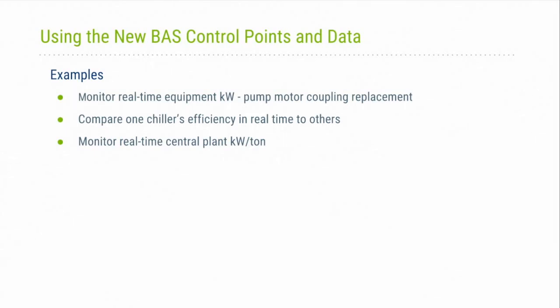And then lastly, the real-time central plant kW per ton value provided at the BAS workstation is useful information for operations and also the regional energy branch office. Here in the regional office, we can use the central plant kW per ton value as a starting point for a remote energy audit of the building. I mean, it's a window into why the building's EUI may be higher than expected. So prior to demand flow, we simply didn't have this level of detailed information available via the BAS for troubleshooting.